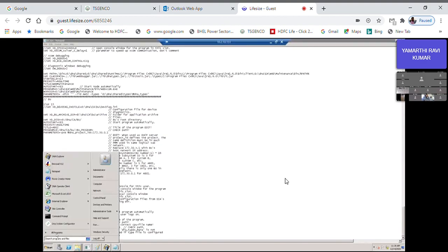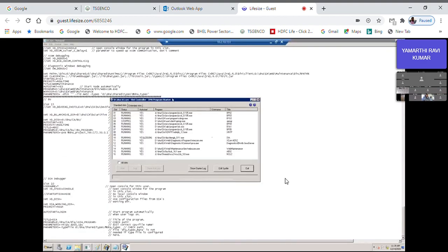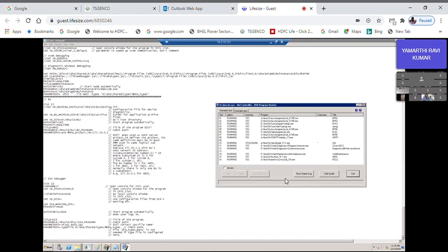This is about a particular system. There is an application called slot controller. Whatever you define in this file will be reflected here. This is an interactive tool to start particular slots. If you see, we have defined 15 as BU, so we can see the backup node here. And always number 16 is your network communication unit. This should first start and become running. Then only will any other slot start up. Otherwise, there is no startup in any other slot.